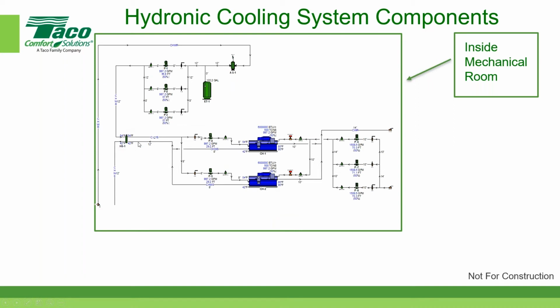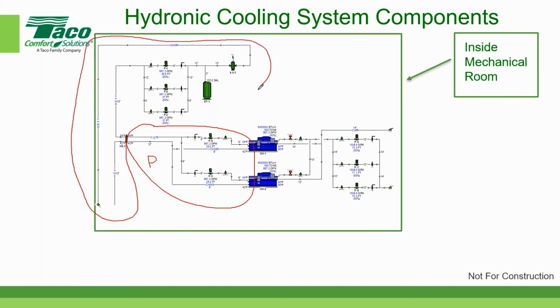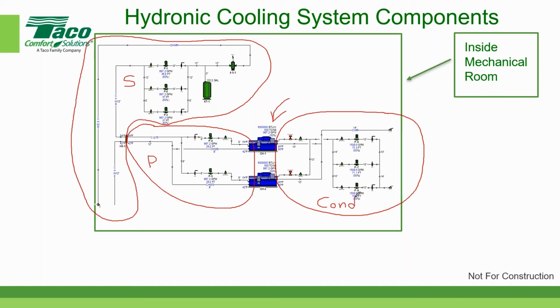We have a hydraulic separator that separates the primary from the secondary. So let me just put a little P here for primary and secondary. Over here, in this general area, is sometimes referred to as the primary pumping system. And this over here, which includes the stuff that's inside the building, which we'll see in a minute, is the secondary side of the pumping system. And then over here on the right, as we already mentioned, this is the condenser water system, because we have two chillers at 50% capacity. You can see they're 500 tons each. So this is the condenser water system, which I'll abbreviate as COND. We have all these different components to talk about. It's really cool stuff.